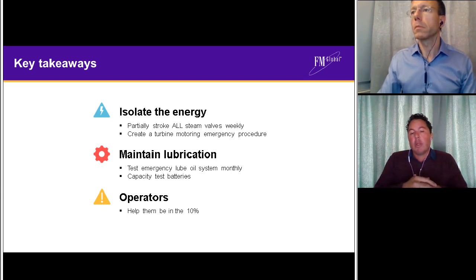They're susceptible to environmental variations. If the temperature's too hot or if the temperature's too cold, it shortens their life. They're susceptible to excessive ripple on the charging current, which also shortens their life. Deep discharge is a problem. So those are the challenges with valve-regulated lead acid batteries rather than flooded. And again, I apologize if that wasn't clear in the presentation.